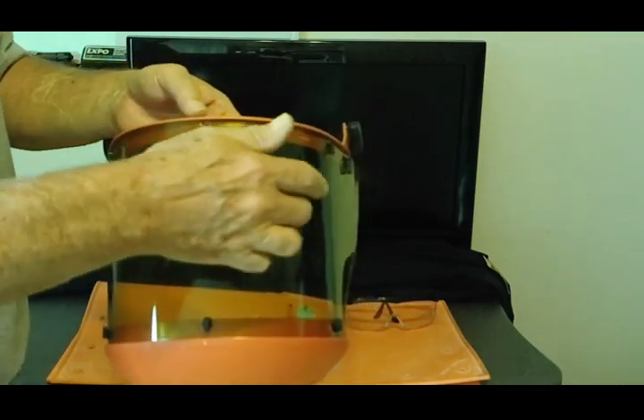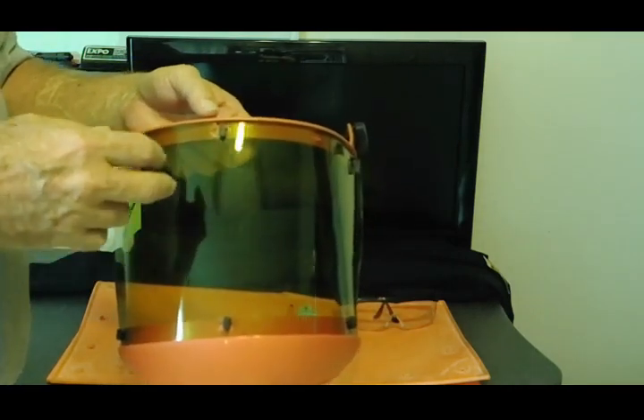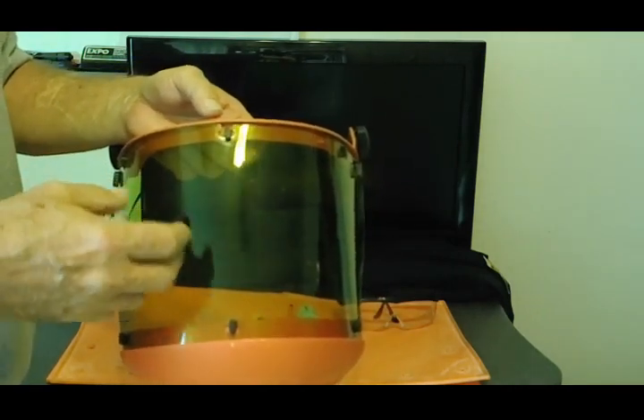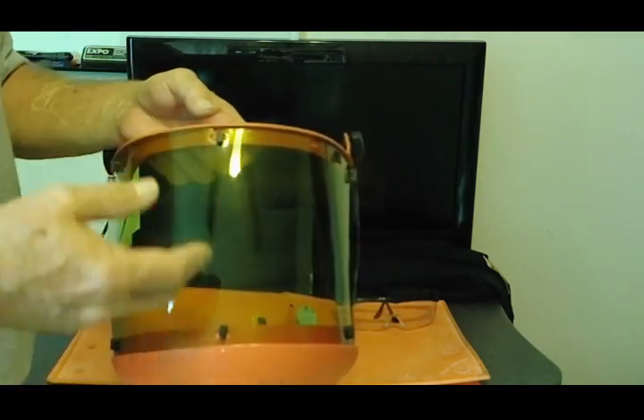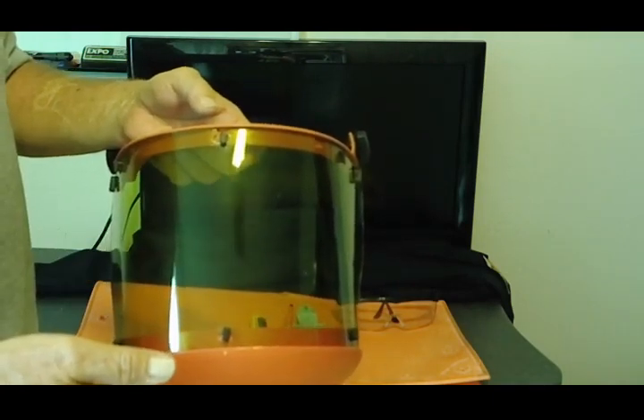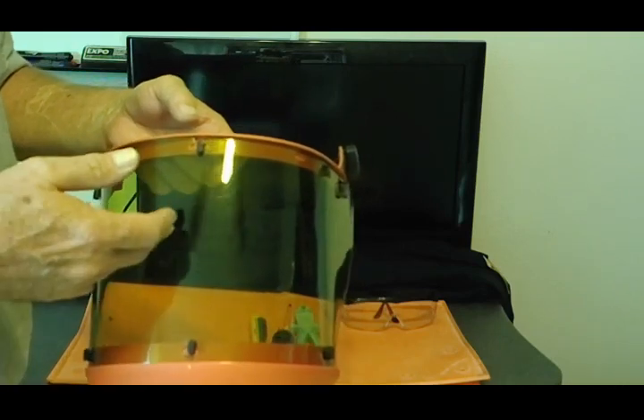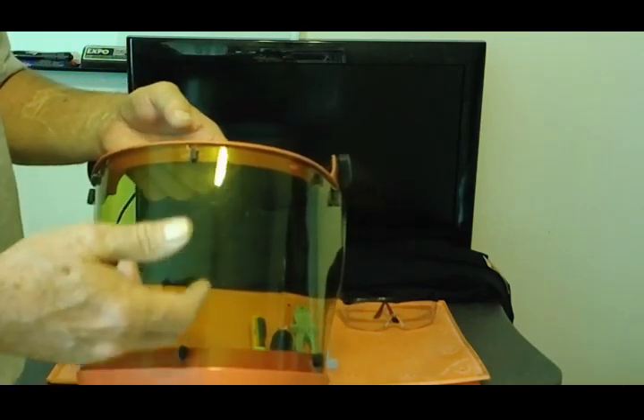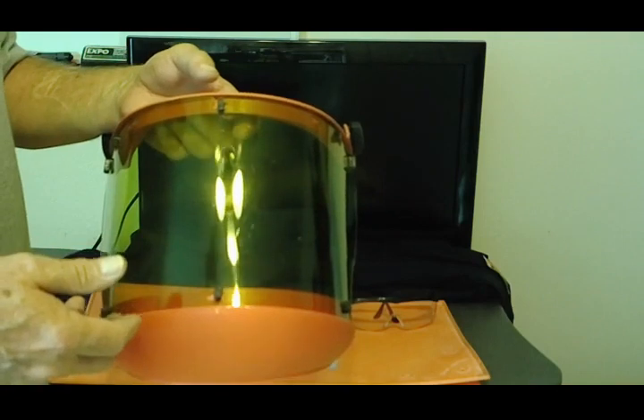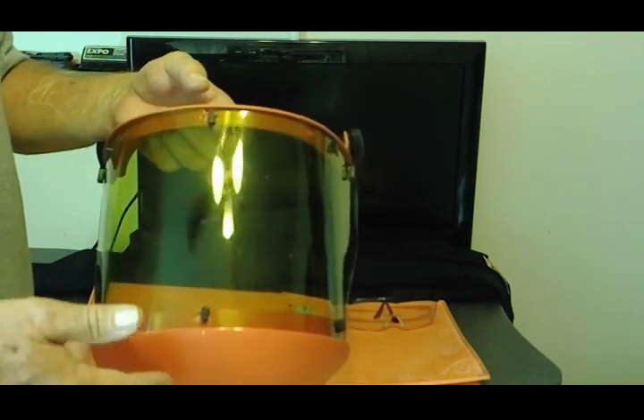So right here, this is protection from heat. But on the downside, this will protect you from arc flash, but if the equipment explodes, large debris might penetrate this face shield. It's not designed to withstand debris, it's only designed to withstand energy.